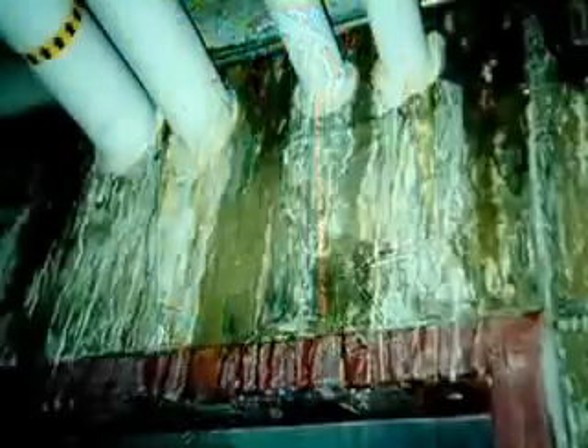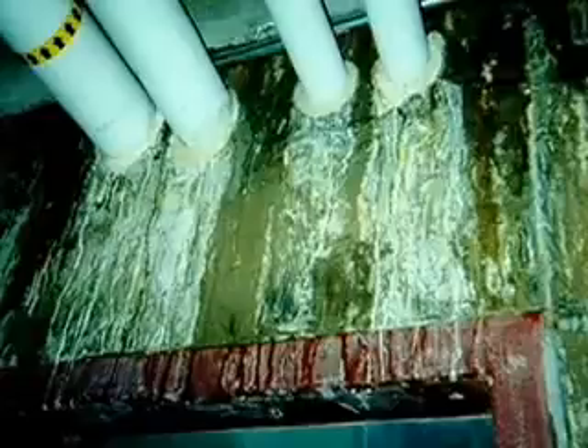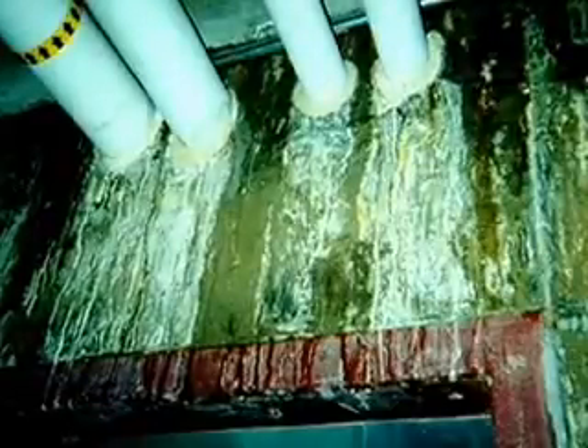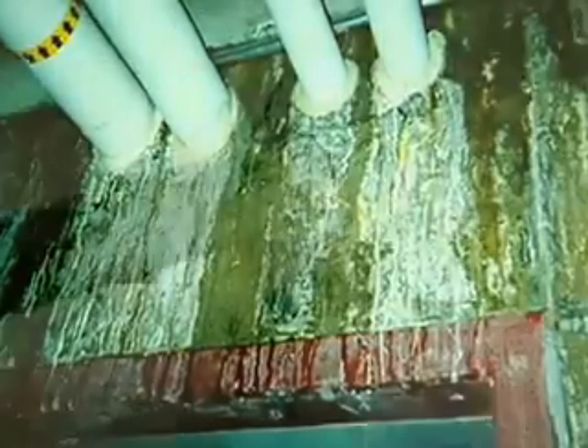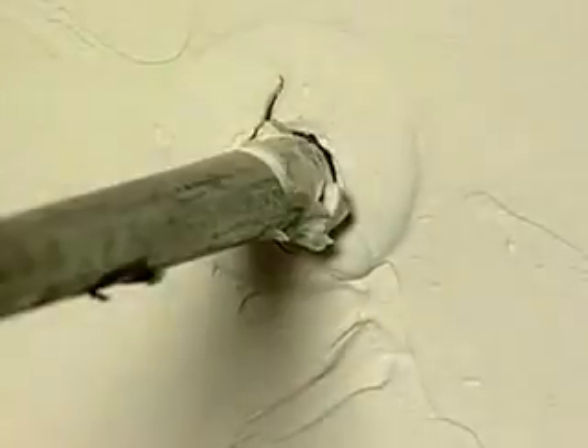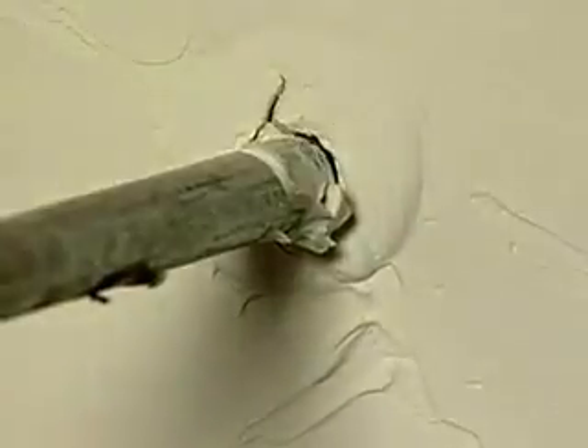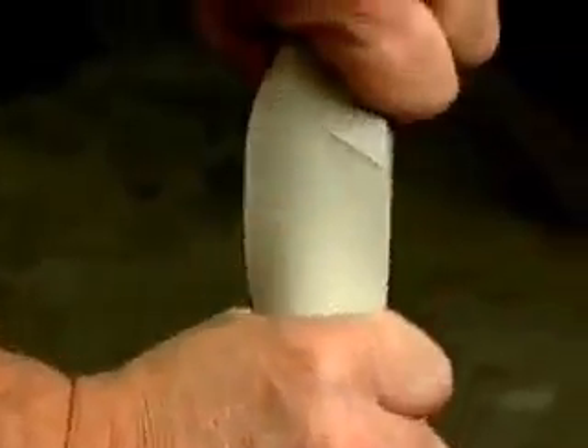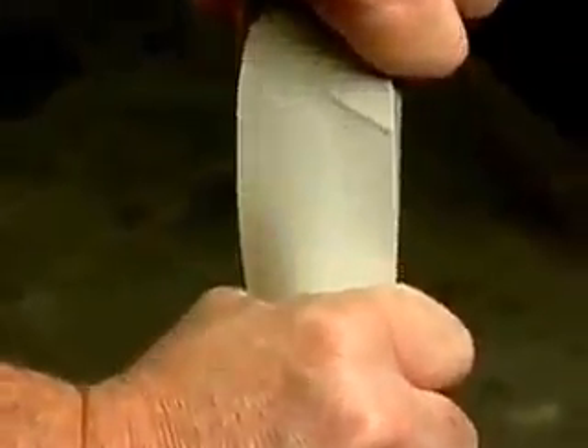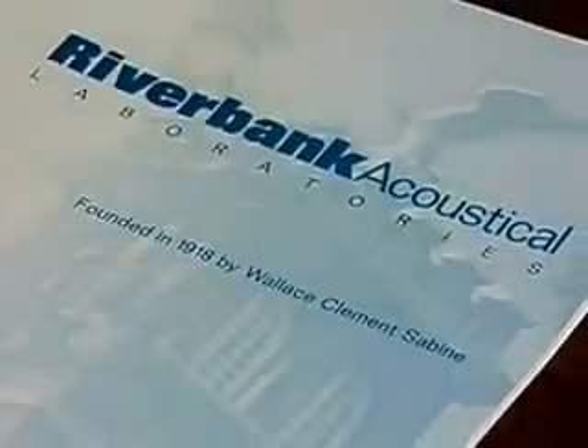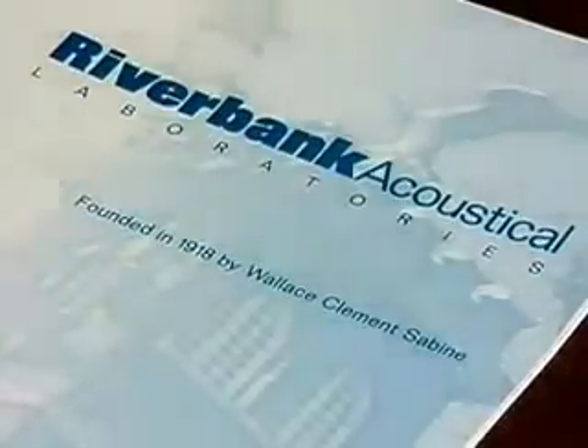Be sure to select products to seal smoke barriers that do not crack or dissolve over time as a result of movement such as pipe expansion and water hammer, or moisture such as ponding or sweating pipes. Hard or brittle materials also conduct sound and will lower the acoustical sound transmission values. So look for materials that are soft and rubbery, and when available, have a published acoustical transmission rating.